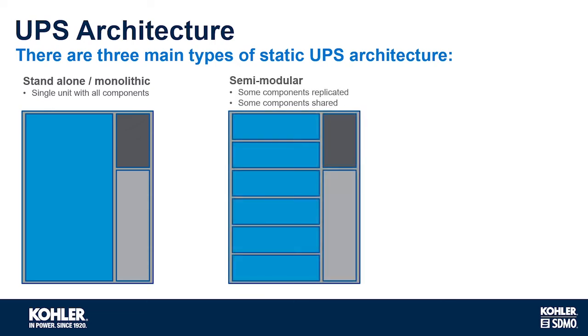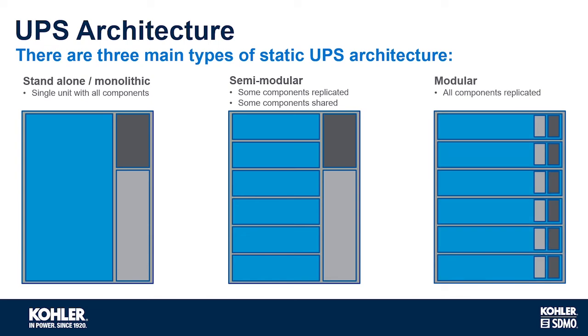And then in the middle, we have what we call semi-modular. This is where some of the components are replicated, such as the inverter and rectifiers, but some components are shared. It's typically the bypass and the controls. And then on the right, we have what we call true modular. This is where everything is replicated. So all the rectifiers, inverters and bypasses are replicated, but also all the controls and all the displays.